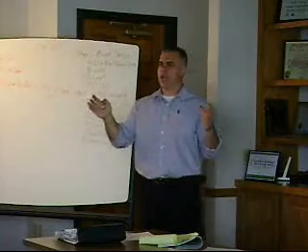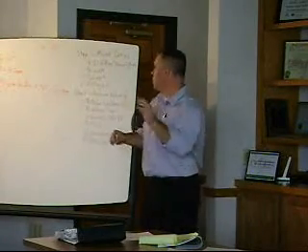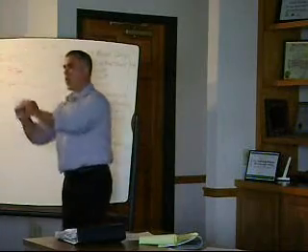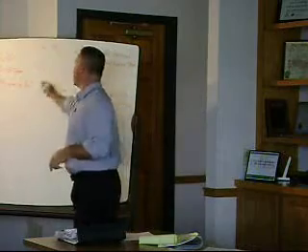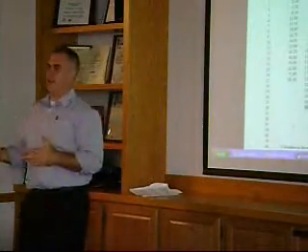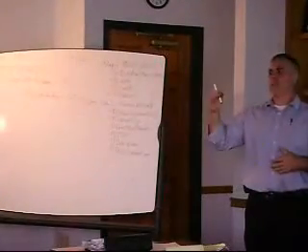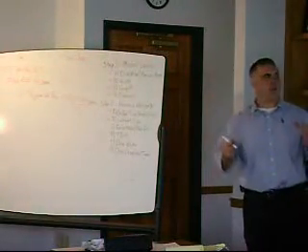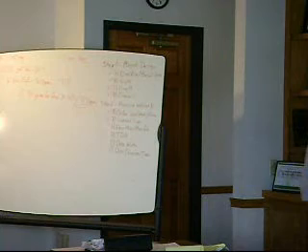You add that all to the total dynamic head, and remember, a pump is designed for two things: flow rate and total dynamic head. How much water do I want to deliver, and how much pressure or force do I have to push it up there to get it there? Total dynamic head. If I've got 16 foot to push against, the pump is getting big. And the bigger it is, the more expensive it is. The more expensive it is, the more expensive it is to maintain and replace. We try to keep our pumps reasonable. That's why a lot of guys shy away from 1.5 line in this example. If you have less force main, you might get away with it.